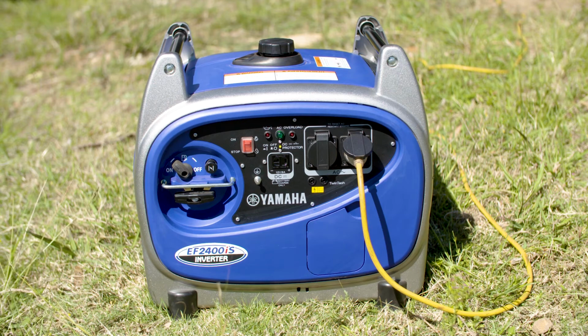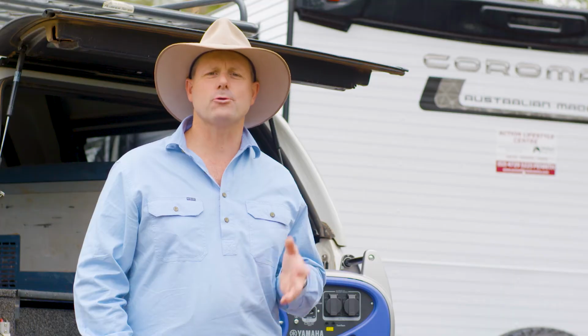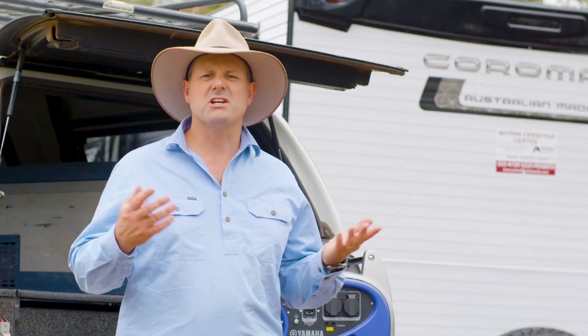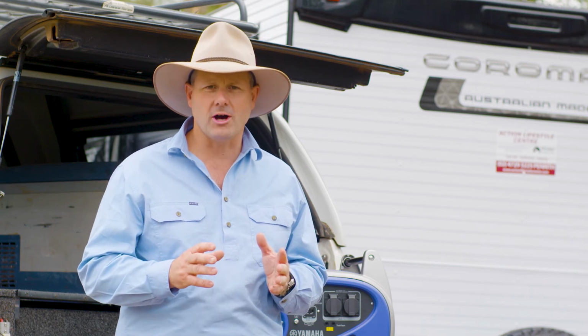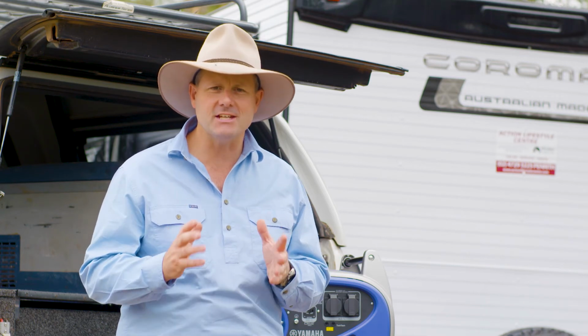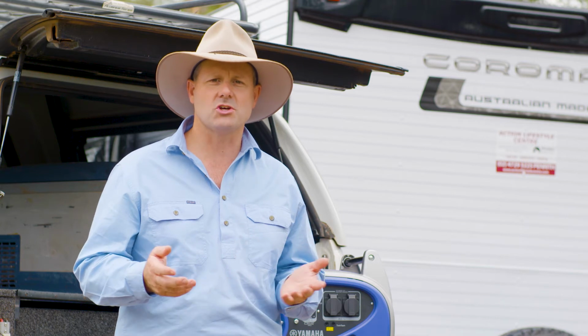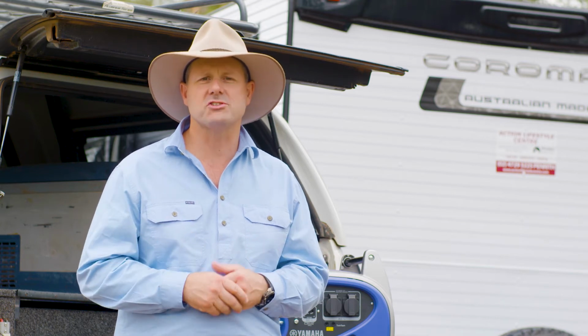The catch is that a generator's quoted power is its peak rating, which it can only sustain for a short time. You have to dig out its continuous rating specification, which is usually about 80% of its peak rating.